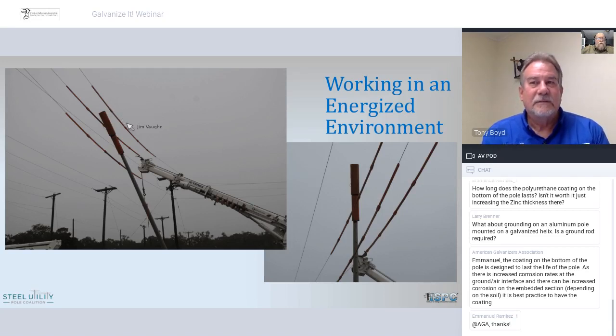And as Tony said, when we refer to hose, we're referring to rubber, which is fairly heavy. They're 5 feet long. They weigh some 9-10 pounds a piece, sometimes depending on what types they are, and they pull down and lower the sag of the conductor, making the space between the conductor and pole closer, which is what Tony was talking about. There are plastic technologies available that weigh less than 25% of the weight of a hose, that can be used and can do the same thing.